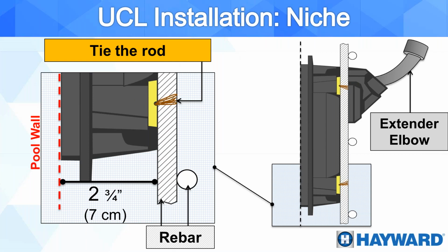With this low profile niche, we're basically just going to attach it directly to our rebar cage without having to do anything special. We can see here that the depth is only about 2¾ inches, and then it has an elbow, obviously, in order to get our wiring going back into the junction box or the transformer. So this is an easier way to install pool-size lights, and it is a safer way because remember, it doesn't require any grounding or bonding, and at the same time, it saves time and money.